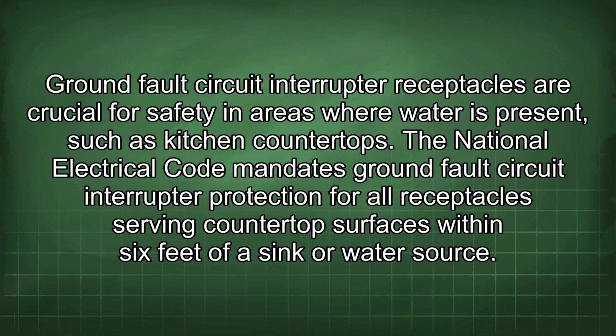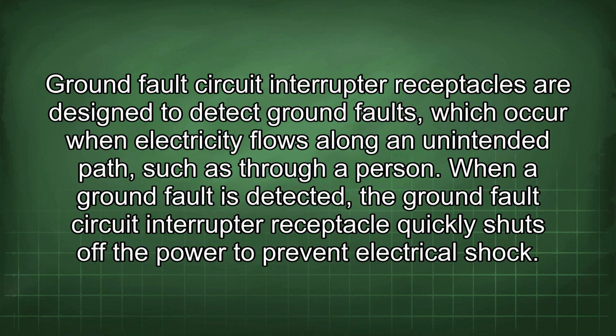The National Electrical Code mandates ground fault circuit interrupter protection for all receptacles serving countertop surfaces within 6 feet of a sink or water source. Ground fault circuit interrupter receptacles are designed to detect ground faults, which occur when electricity flows along an unintended path, such as through a person. When a ground fault is detected, the ground fault circuit interrupter receptacle quickly shuts off the power to prevent electrical shock.